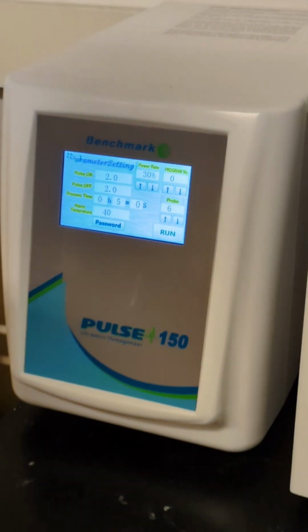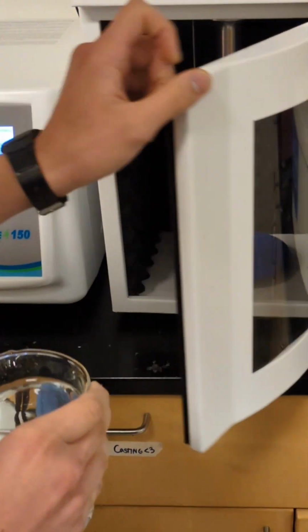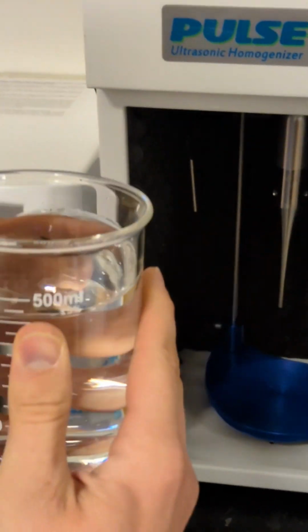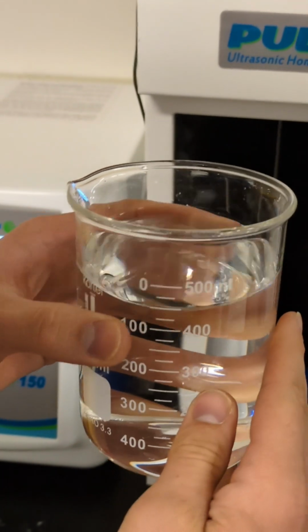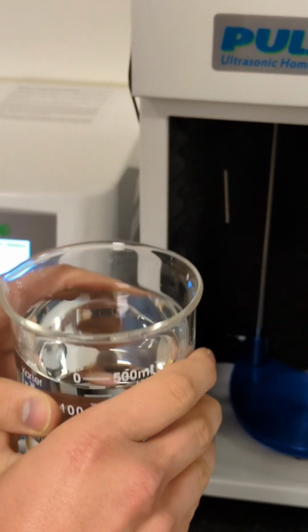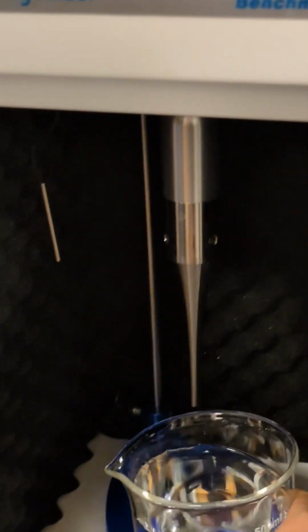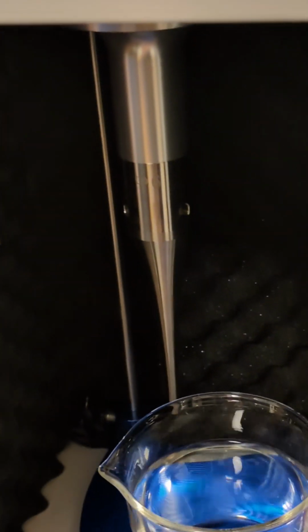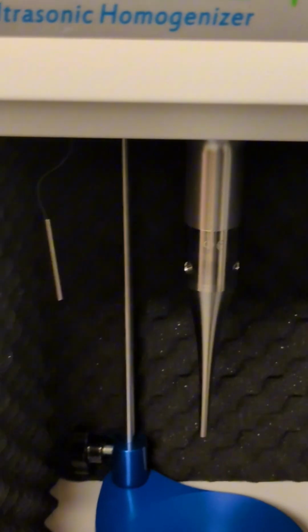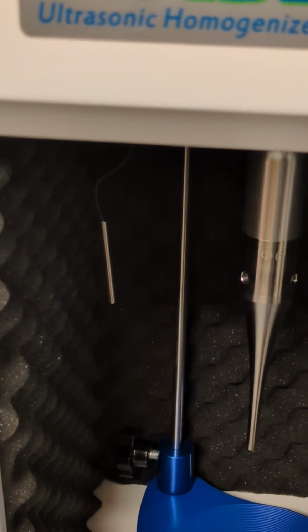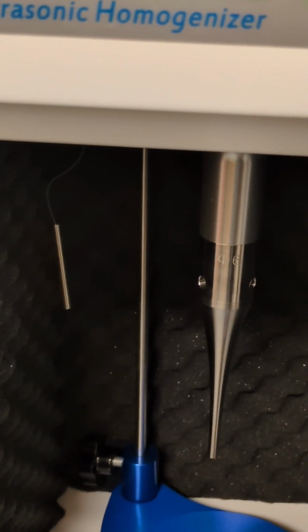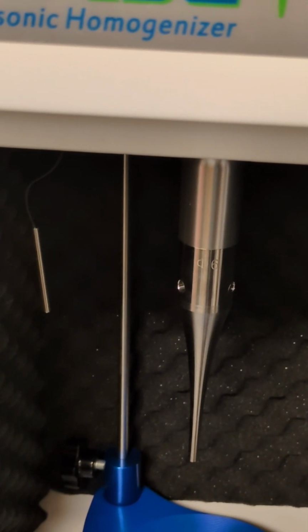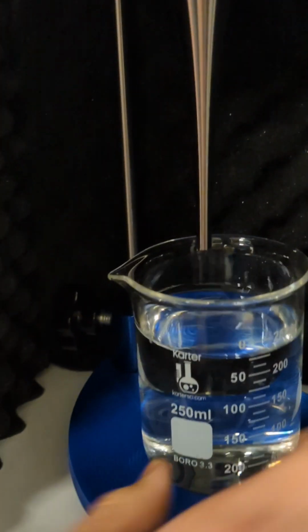So now we need to put our sample in. This should be between 50 to 500 milliliters. Really, the important part is that the horn can fit inside it. That can be submerged 2 to 3 centimeters while still having plenty of room at the bottom and sides so that it's never near any of the solid surfaces, because it's very delicate and pretty much any physical contact with another solid object may damage it if you're not careful. So just make sure nothing ever touches it.